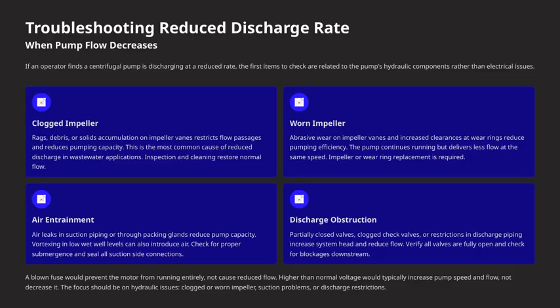When you notice that a centrifugal pump is discharging at a reduced rate, the first thing to do is focus on the hydraulic components of the pump rather than the electrical parts. Often, the issue stems from something obstructing or impairing the flow within the pump itself.